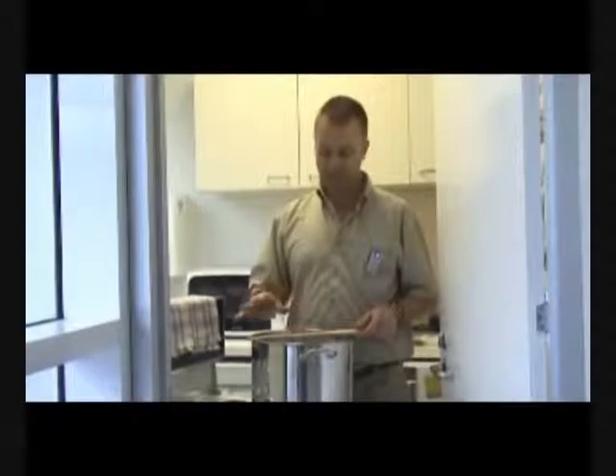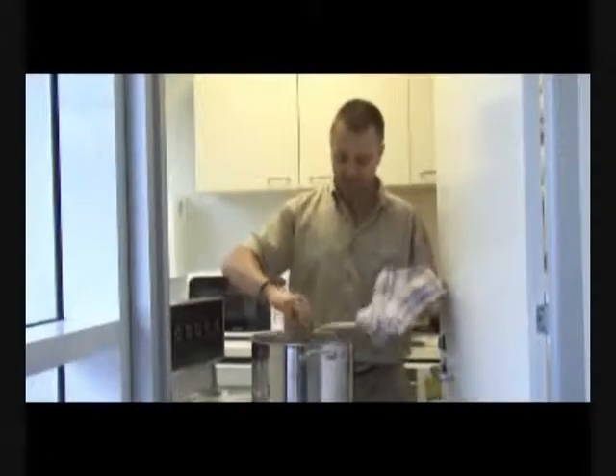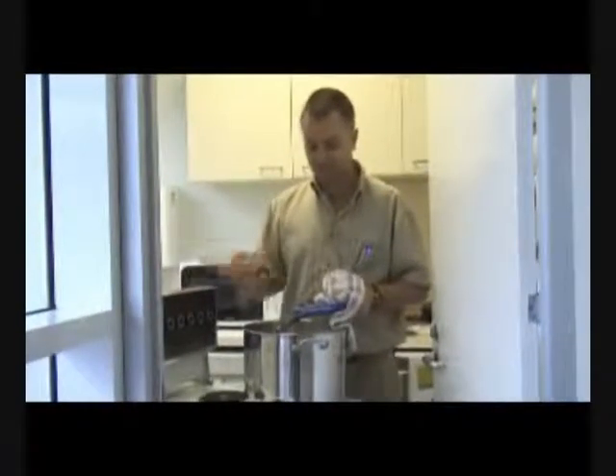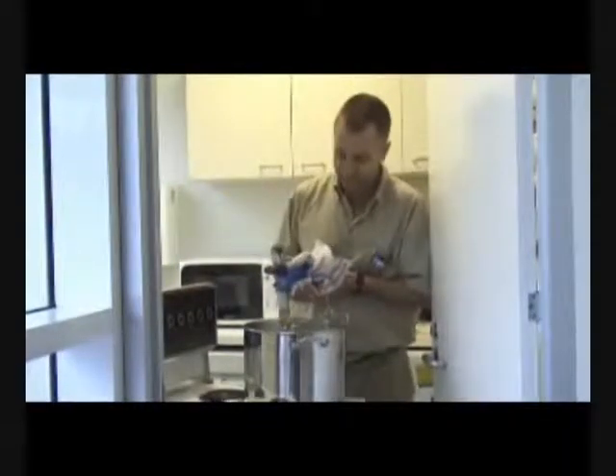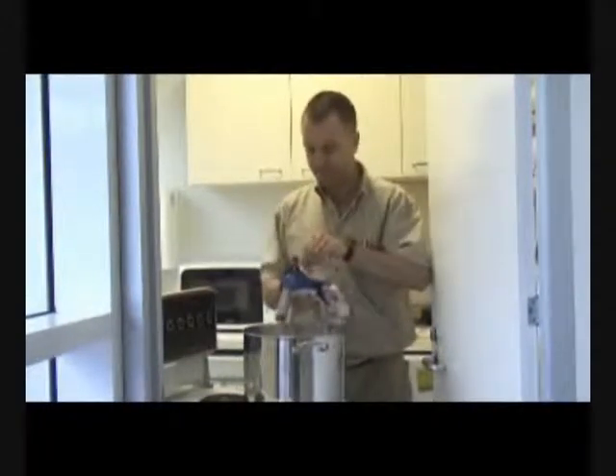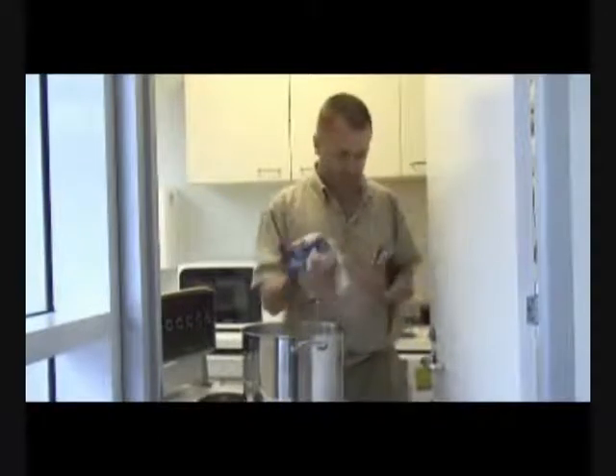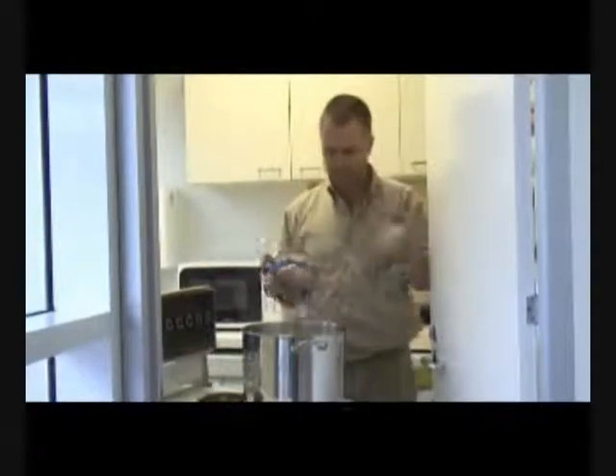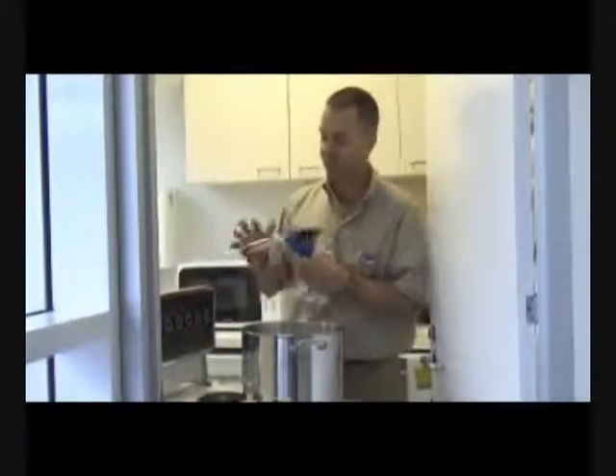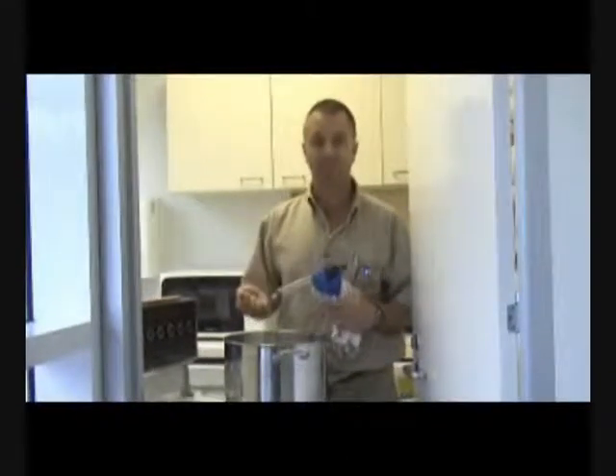Okay, this instrument has been in the water here. It's boiled for about 20 minutes. So when you remove the instrument, remember it's going to be very hot. So I've got a dry cloth. So I pick it up, remove the spoon or the stick, whichever you've got across the pot there, and just carefully, I've expelled all the water. I can then take the wire, in this case, off the applicator. So that's now ready. That applicator, it's been boiled. The needles are in here, so I can just drain the water out and get the needles out of the pot, and then the whole instrument's ready to take and use.